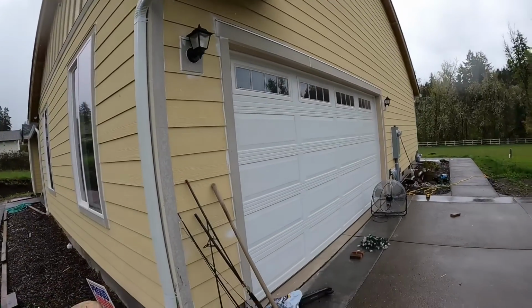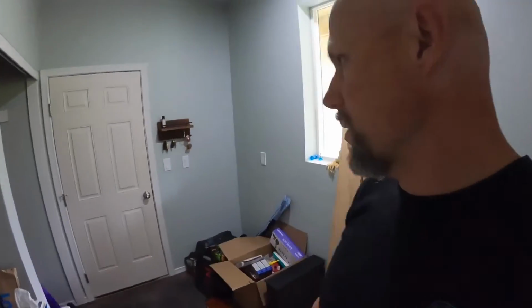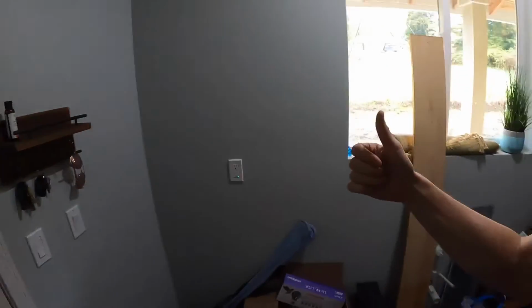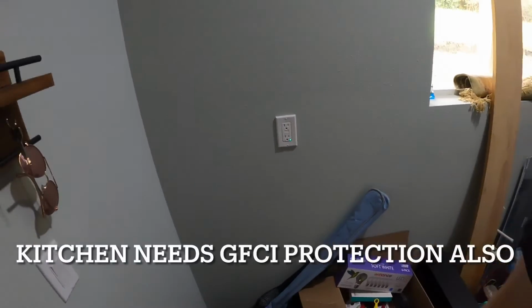So now we're going to go inside and look at that. The electrical inspector is going to be looking to see that all the outlets, such as your dryer outlet, so 240, and your switches, 3-ways, work. They'll come through, test every switch, and make sure all the trim's on. So here we've got all the trim plates on and that sort of thing. Seeing if certain areas such as the bathrooms, the laundry rooms, all of the garage, and that sort of thing, and all the exterior outlets are all on GFCI breakers like this, okay?